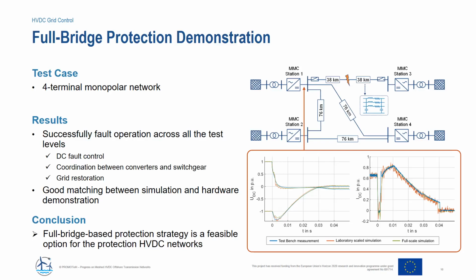So once a fault occurs, the DC voltage collapses on the positive pole. This is the top pole, and the converters detect the fault and start to reduce their current flowing from the AC to the DC system to values close to zero very quickly. However, after the fault is located at this line, the converter station M1 switches into a so-called terminal voltage control mode. The purpose is to quickly discharge the system in order to create near zero current as well as near zero voltage conditions for the residual current switch as fast as possible. And here, after around 40 milliseconds, the conditions are fulfilled and the residual current breaker can separate the faulted line.